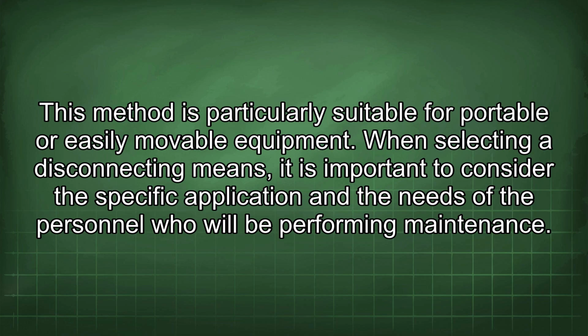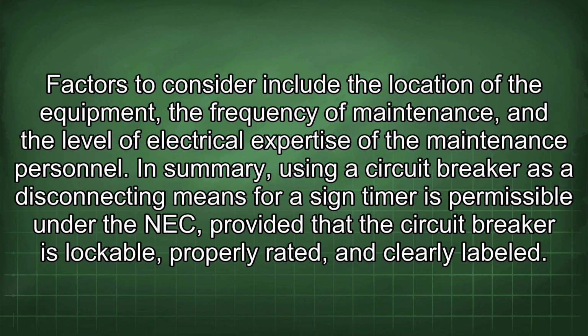When selecting a disconnecting means, it is important to consider the specific application and the needs of the personnel who will be performing maintenance. Factors to consider include the location of the equipment, the frequency of maintenance, and the level of electrical expertise of the maintenance personnel. In summary, using a circuit breaker as a disconnecting means for a sign timer is permissible under the NEC, provided that the circuit breaker is lockable, properly rated, and clearly labeled.